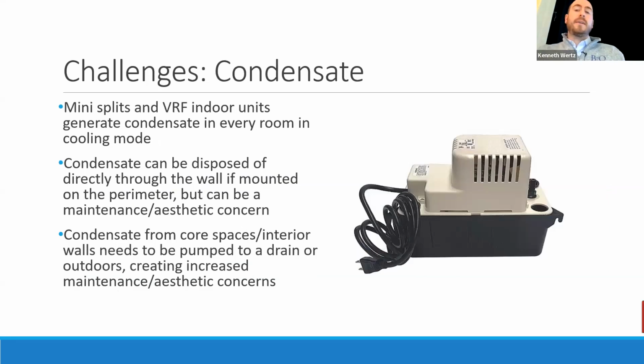All right, condensate. I'm sure everybody's familiar with these little units here. When you've got a mini split or an indoor VRF unit in cooling mode, if the room is humid enough, it's going to generate condensate, and it's going to pool in the bottom of this pump, and then it's going to get pumped out. It needs to go somewhere. And a lot of the units have these built into them. You don't necessarily have to buy a second one.